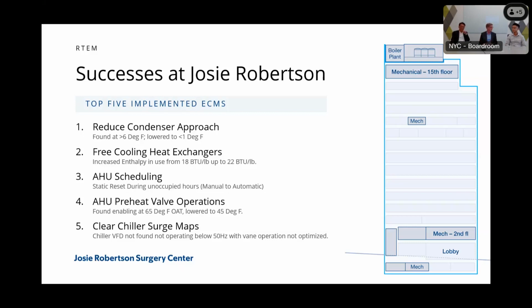The free cooling was another success at the Josie Robertson Center. For those of you not familiar with the BTU per pound measurement, we actually were able to push free cooling above 53-degree wet bulb, if that's more your flavor of measurement, which is very impressive. Some of that is working with the site. Some of that is Jonathan himself, where he was able to push some of the supply air temperatures within the site through rigorous cooling coil maintenance and other various forms of maintenance at the site.